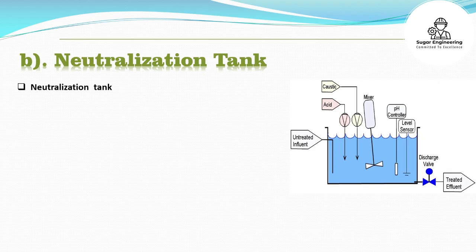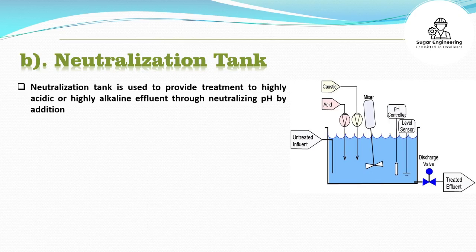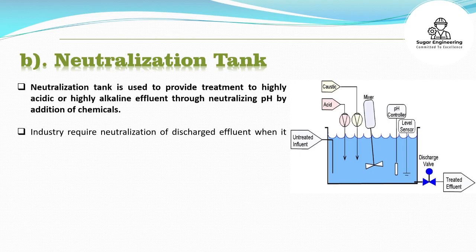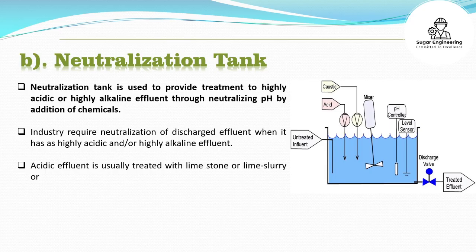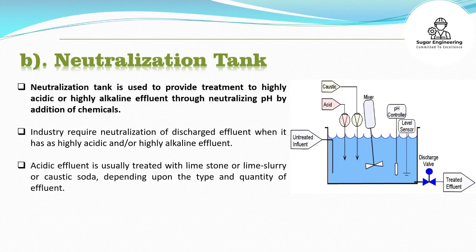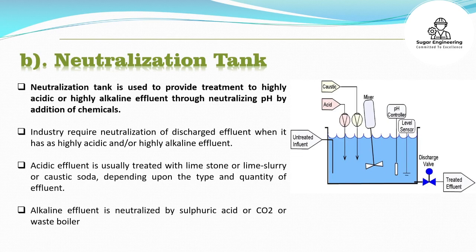Neutralization Tank is used to provide treatment to highly acidic or highly alkaline effluent through neutralizing pH by addition of chemicals. Industries require neutralization of discharged effluent when it has highly acidic and/or highly alkaline characteristics. Acidic effluent is usually treated with limestone, lime slurry, or caustic soda, depending upon the type and quantity of effluent. Alkaline effluent is neutralized by sulfuric acid, CO2, or waste boiler flue gas.